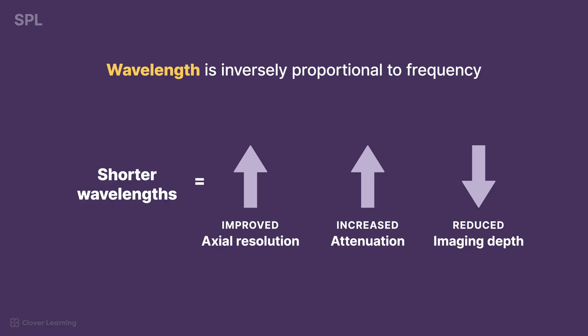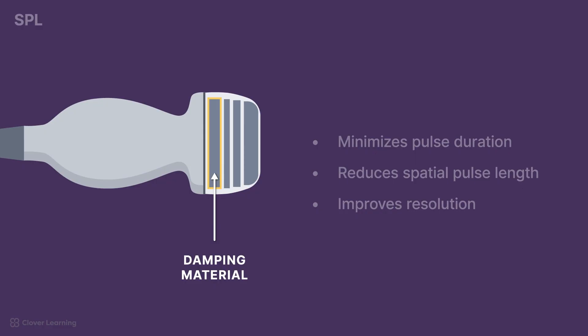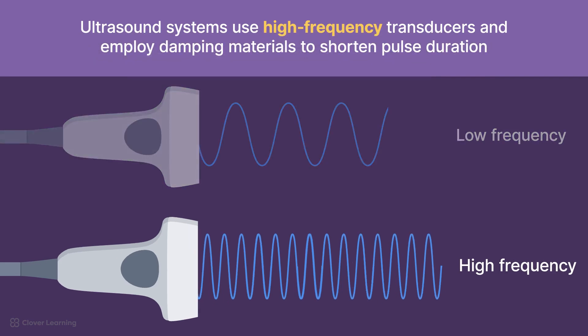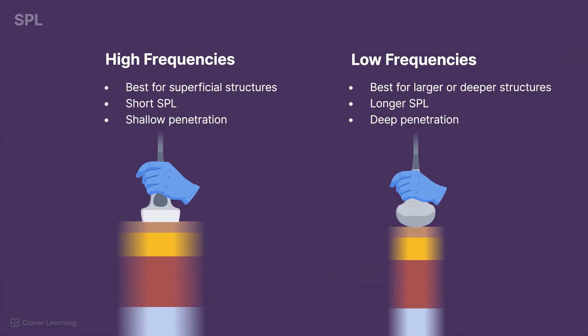As a result, there is a trade-off between resolution and imaging depth, requiring careful selection of transducer frequency based on the clinical application. The damping material within the transducer minimizes pulse duration, which reduces spatial pulse length and improves resolution. To optimize axial resolution, ultrasound systems use high-frequency transducers and employ damping materials to shorten pulse duration. This optimization is particularly beneficial when imaging superficial structures and small organs that require fine detail. Remember, the need for deep penetration is minimal for superficial structures, so higher-frequency transducers with shorter spatial pulse length are suitable for these images.